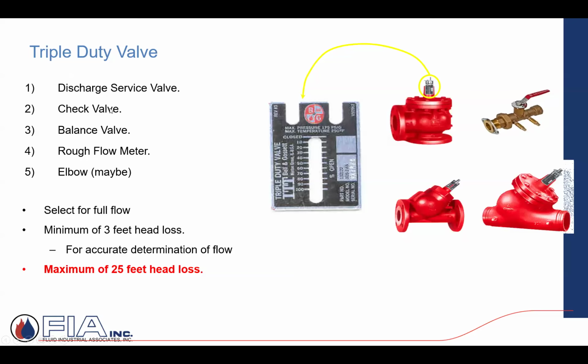And here's just a little bit of a checklist. Service valve, check valve, a throttling, a balance valve, possibly also a flow meter. And then depending upon the orientation, some of them are straight through, others could be used as, right here, they're showing as an elbow.